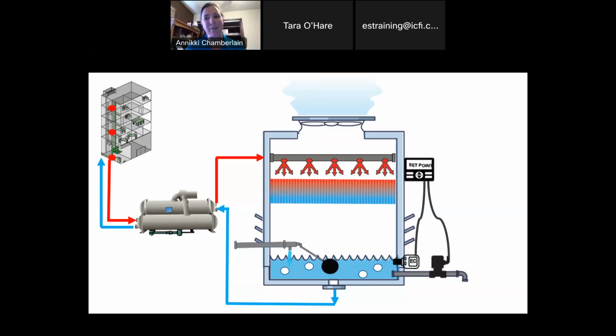Typically this is just like a float valve like you might see in the back of your toilet. Just mechanically, once the water drops, it turns on the water flow, and then once it gets back to a particular level, the water stops. And just in case that makeup valve gets stuck on, we have an overflow valve, or an overflow pipe. So very similar to your bathtub, right? You're going to run a hot bath, you start making spaghetti and you forget you've got a bath running. There's that little hole in the bathtub to make sure you don't flood your bathroom. That's the same as an overfill valve.